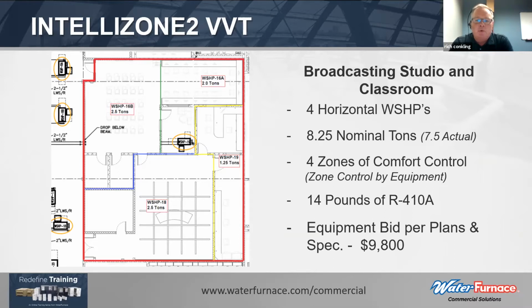As I mentioned, these 4 units provide us with only 4 zones of comfort control, and it requires 14 pounds of R410A. And I started putting pounds of refrigerant onto some of these presentations because as we start moving into A2L refrigerants in the future, that's going to be something we're going to be obligated to manage and minimize. And then per the equipment plans and specifications, our bid would be right under $10,000.